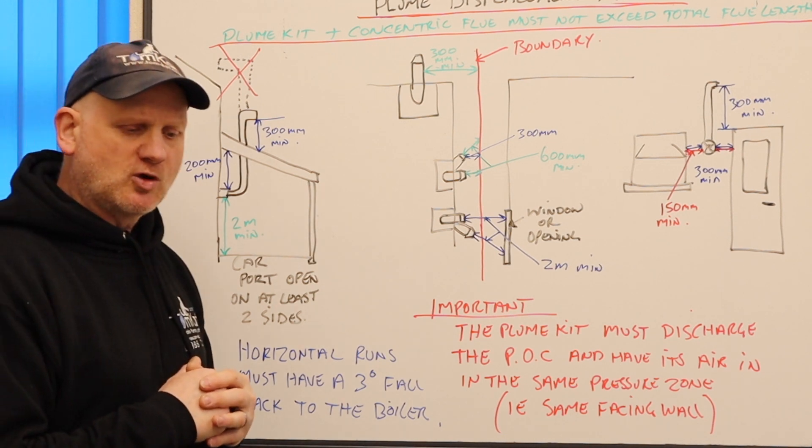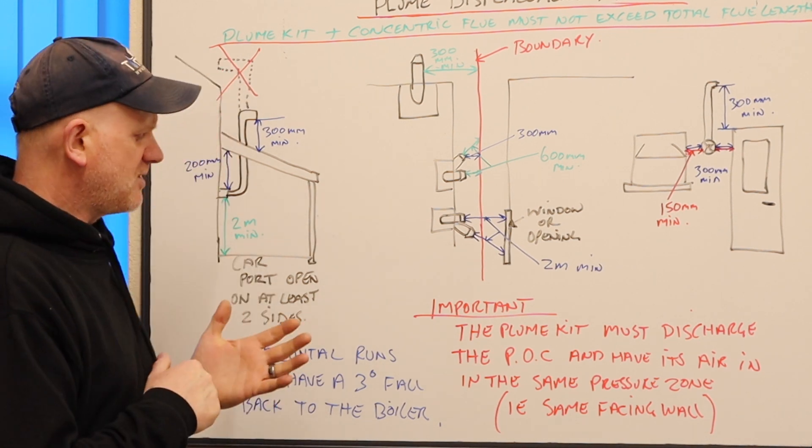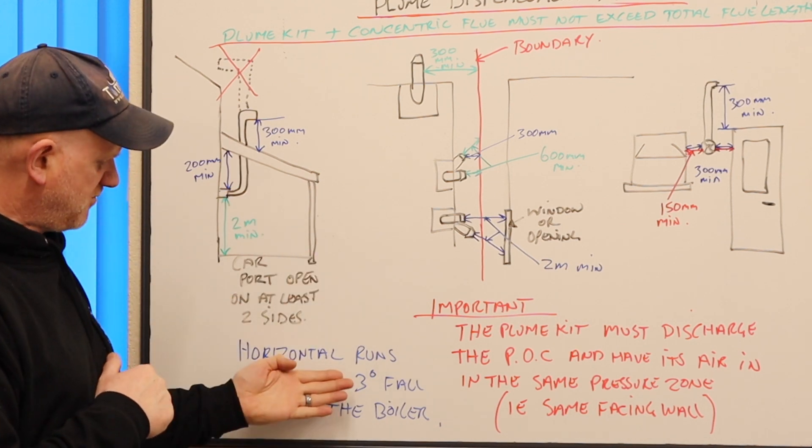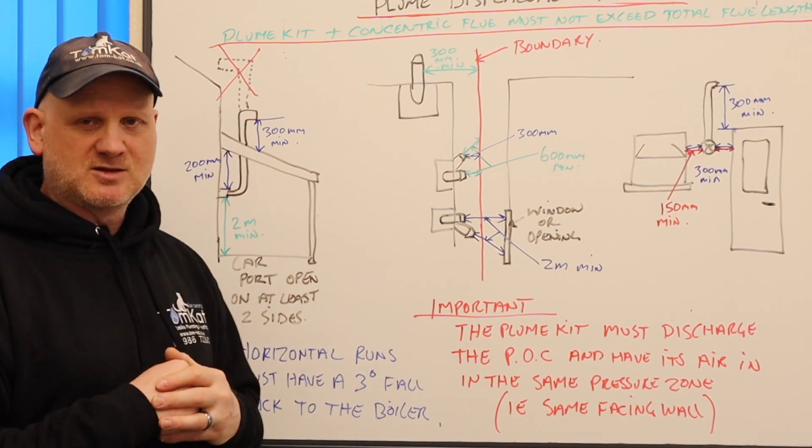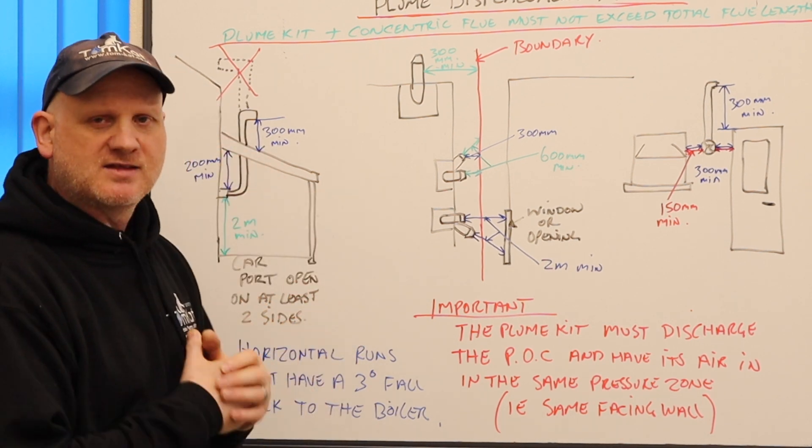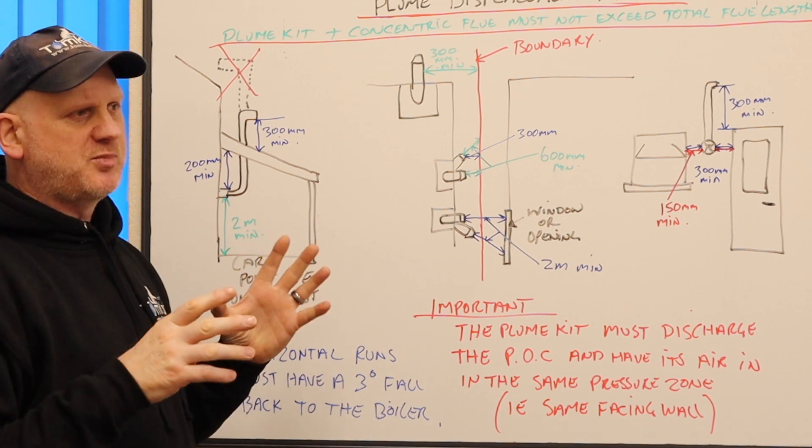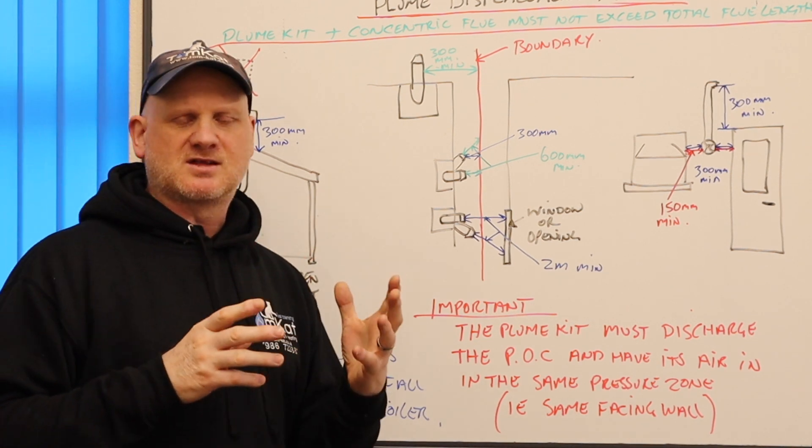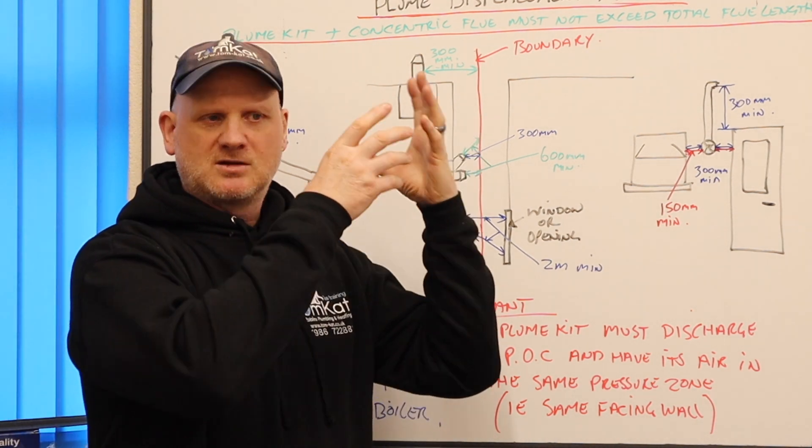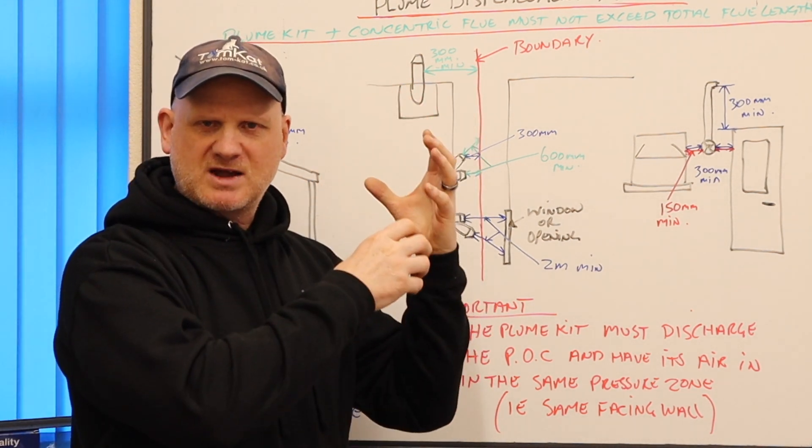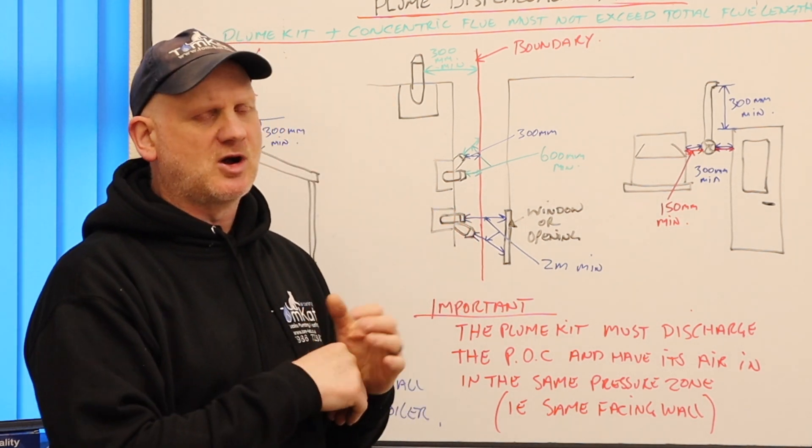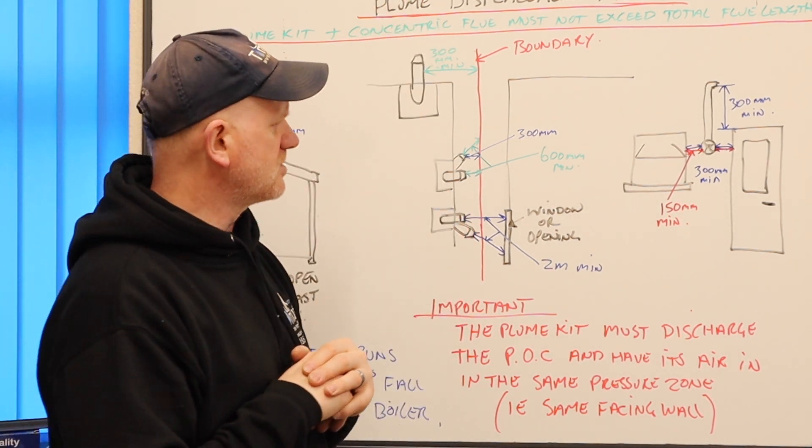Also, if we have any horizontal runs on this flue system, now it says between one and a half degrees to three degrees like I've put here falling back to the boiler because it needs the water to go back down the condensing drain. What this pluming kit does is basically because of its height it makes the condense go back to water again so most of it goes back down into the boiler rather than coming out as a pluming nuisance.